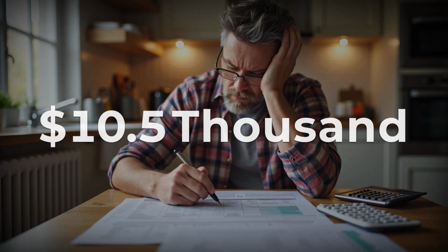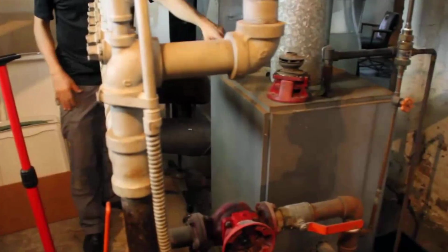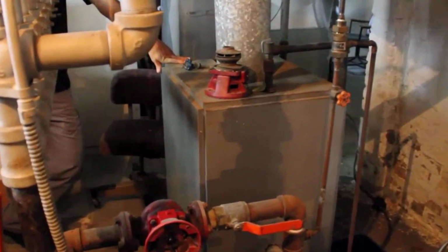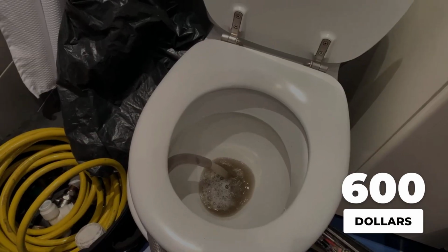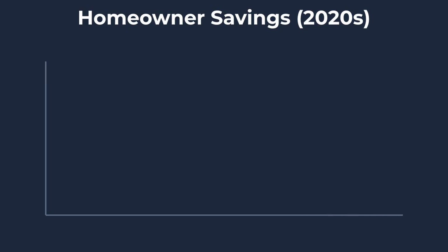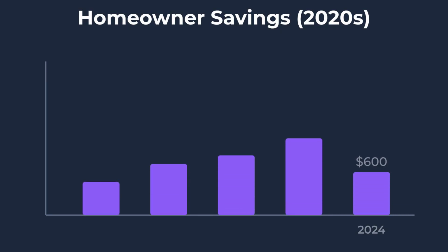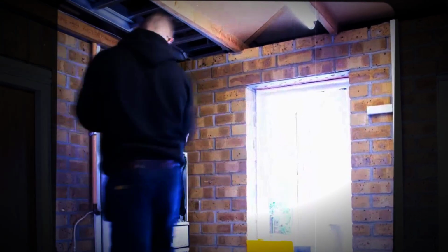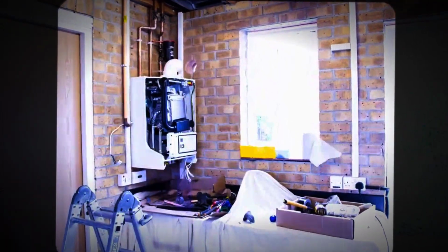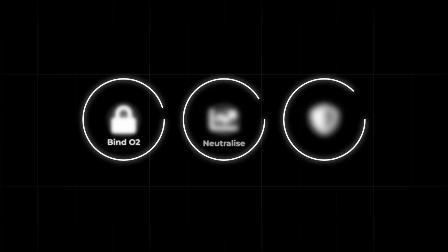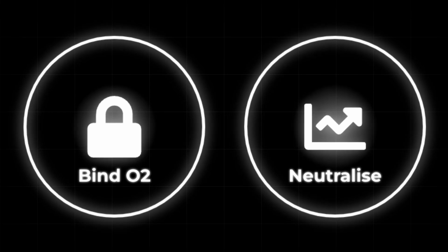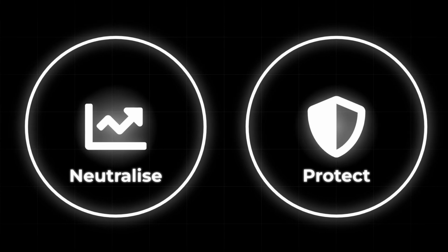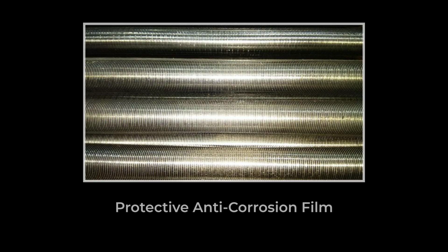Compare that to the $10,500 replacement quote one Boston homeowner got for a 15-year-old Weil-McLain. The real fix is a $600 power flush and a bottle of inhibitor. That is $9,900 that stays in your pocket, and a boiler that runs another 10 to 20 years with proper upkeep. But the job is not done after the flush. The real trick is adding a chemical inhibitor, a colorless solution that binds up oxygen, neutralizes corrosive minerals, and coats internal metal with a protective film.